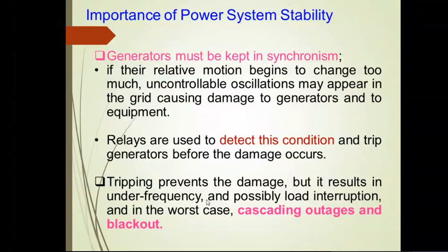And then if one generator goes outage, at that moment you have only 4 generators here. The load remains connected. The load is 2500 megawatt, but one generator goes outage. So now the total generation which is remaining is 2000 megawatt only, and thus the frequency will drop further, and this will result in a worst case here, if we do not have load interruption.